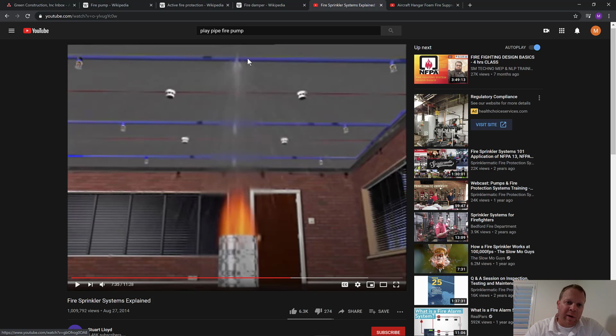Another scenario could be where this is open. All of these sprinkler heads do not have any kind of little bulb in them. They're all open, and the pipe is completely dry. Then the fire alarm system, a smoke detector, or some flame detector, or a combination of multiple of them, indicates that there's a fire in the space. Then that deluge valve opens up and sends water, and this entire area will get completely saturated, because none of the sprinkler heads have the bulb. They would all be letting water out. So there's lots of different ways.